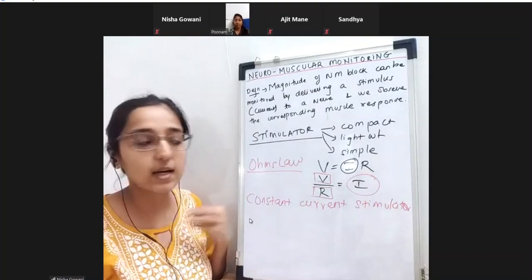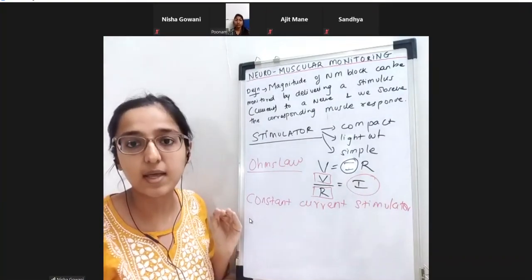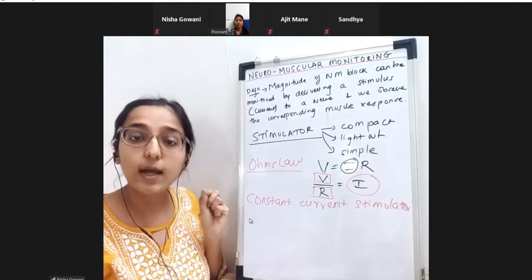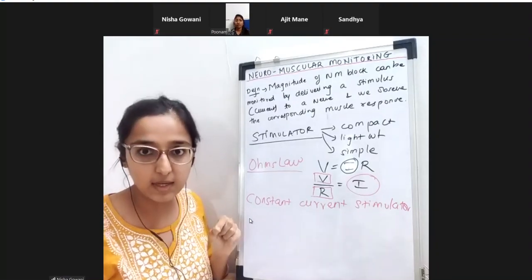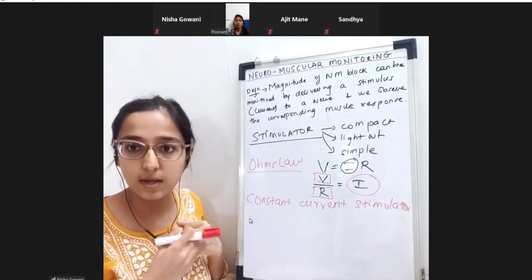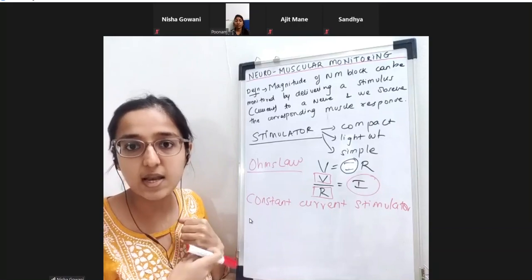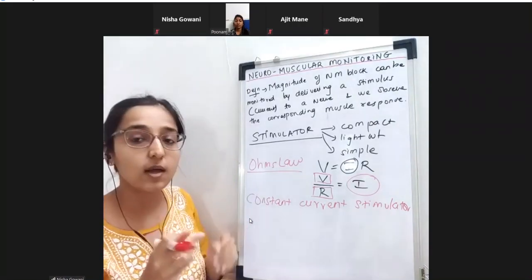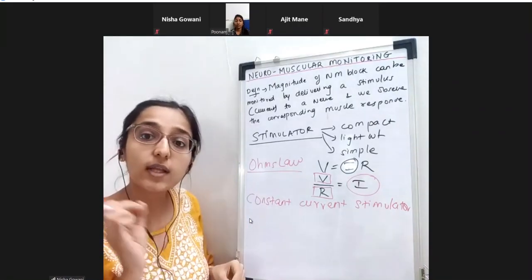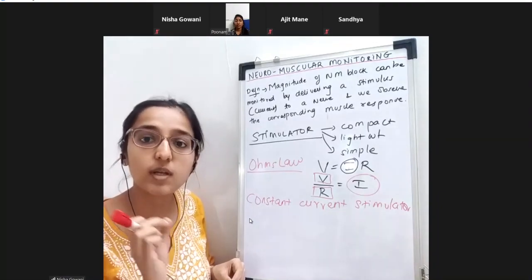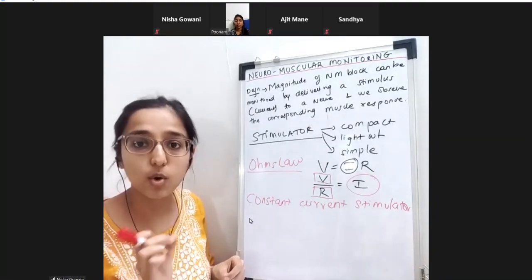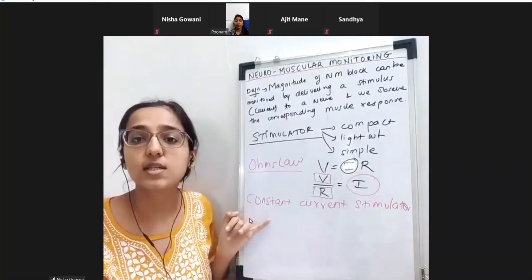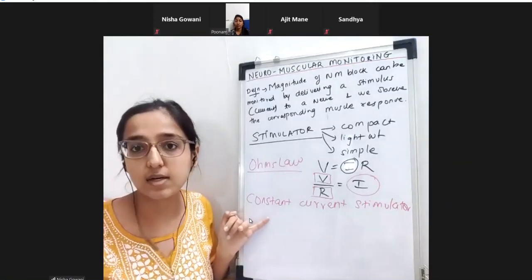If I select 20 mA on the nerve stimulator, it will give 20 mA. It will sense the resistance offered by the skin and tissues, alter the voltage accordingly, and ensure that 20 mA only gets delivered - not more, not less. The stimulator we are using is a constant current stimulator and it follows Ohm's law.